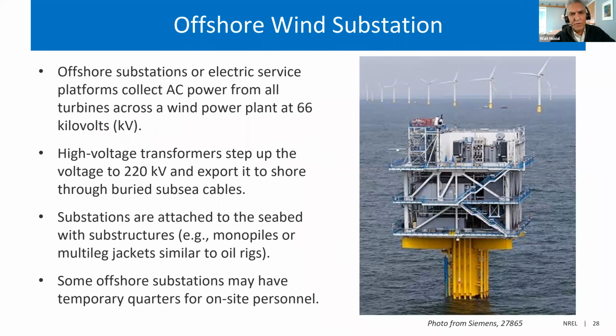Now I'll talk about the substations, where all the power is aggregated. The turbines all connect to one of these substations, which collects power at about 66,000 volts from the turbines' own transformers. From there it's stepped up further to about 220 kilovolts, aggregated together, and sent through an export cable buried in the sea to shore, where it connects to the land-based grid.